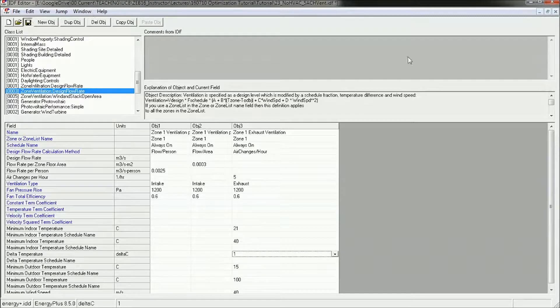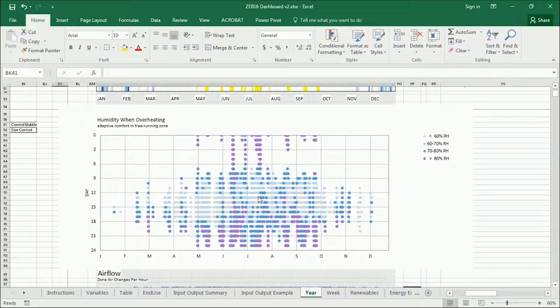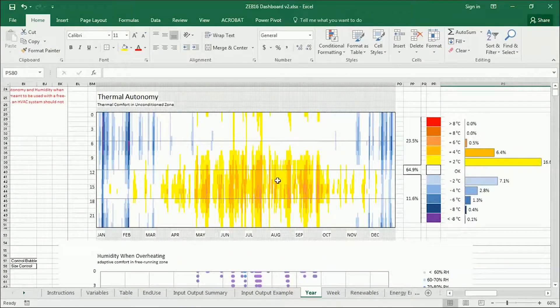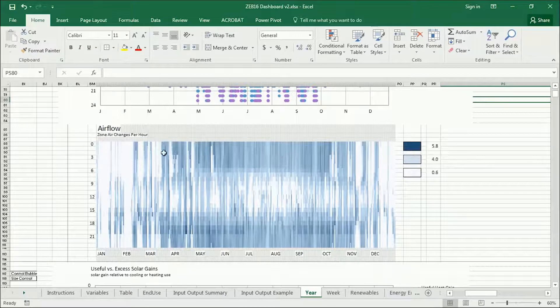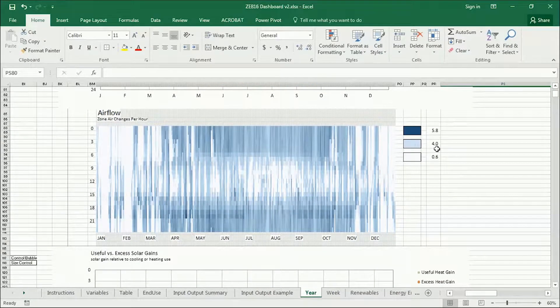So it's done simulating. I pasted the variables into my dashboard and now you can see that the number of hours of overheating has been dramatically reduced, because we've got a lot more air moving through the zone — it's not a closed-up greenhouse anymore. If you go down to the next graph, this airflow describes when that fan is running. You can see that we're getting as high as 5.8 air changes per hour, because we've got 5 air changes per hour plus infiltration plus the fresh air.